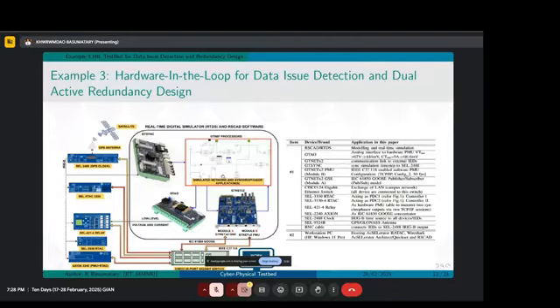After getting enough confidence while executing the first and second examples, we are shifting to testbed development for example 3, where we have the synchronizing clock, SEL-3350 and SEL-421 relay, which is acting as a PMU here, and a real SEL-3530 RTAC again. That is the simulated network where we take the IEEE 39 bus system, where we have PMUs, real hardware that we are integrating, and the embedded PMU in the RTDS also.